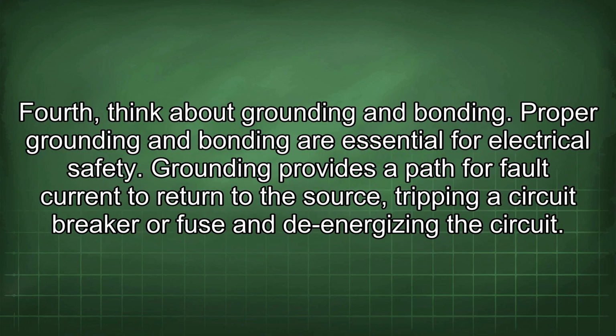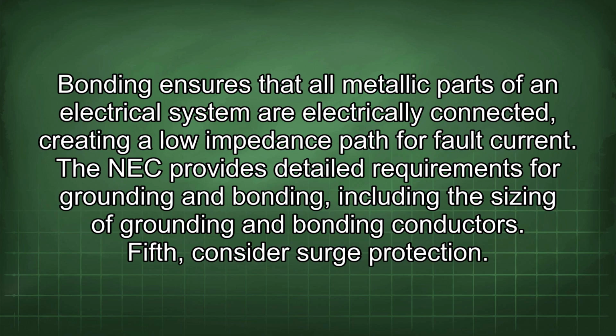Fourth, think about grounding and bonding. Proper grounding and bonding are essential for electrical safety. Grounding provides a path for fault current to return to the source, tripping a circuit breaker or fuse and de-energizing the circuit. Bonding ensures that all metallic parts of an electrical system are electrically connected, creating a low impedance path for fault current. The NEC provides detailed requirements for grounding and bonding, including the sizing of grounding and bonding conductors.